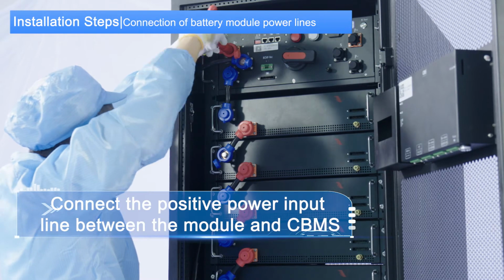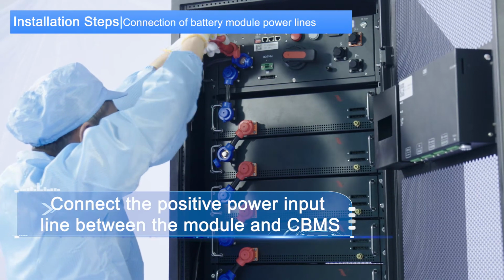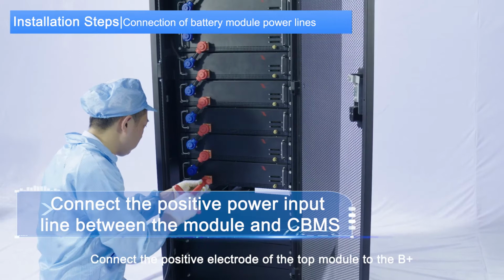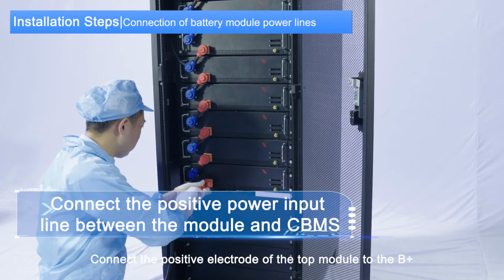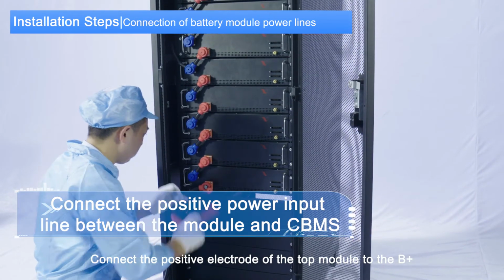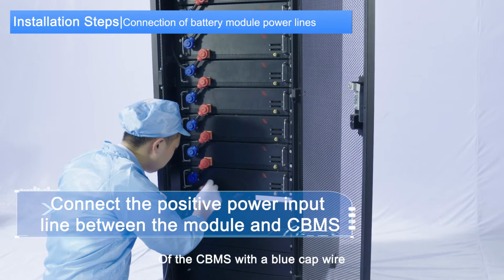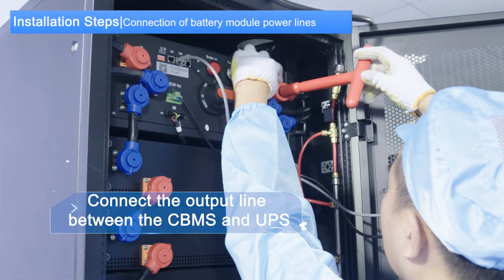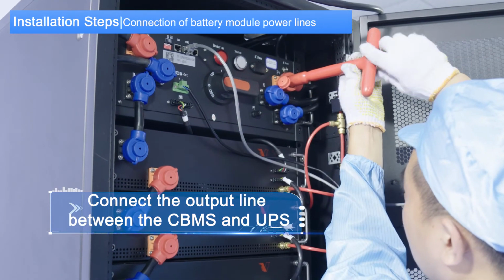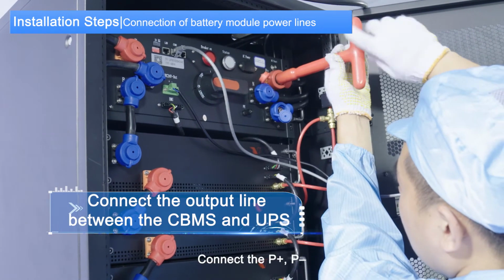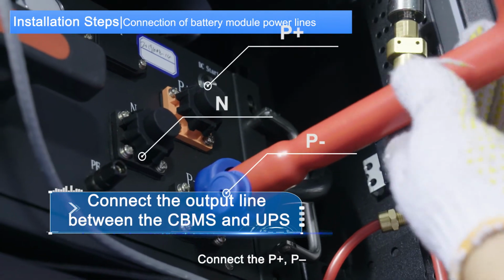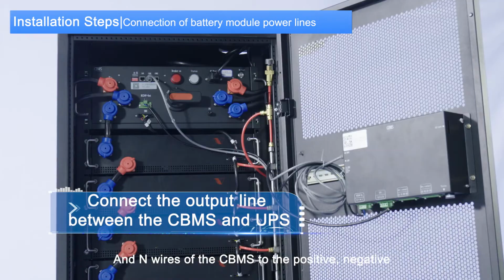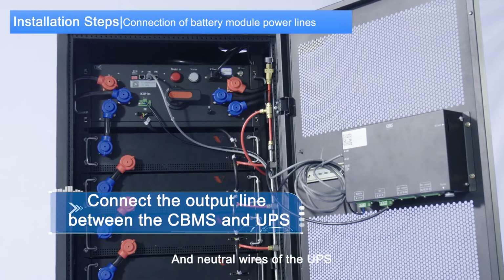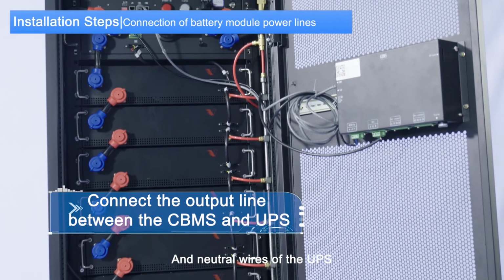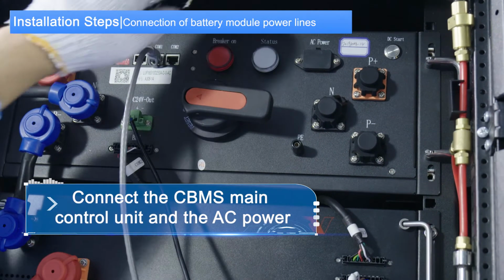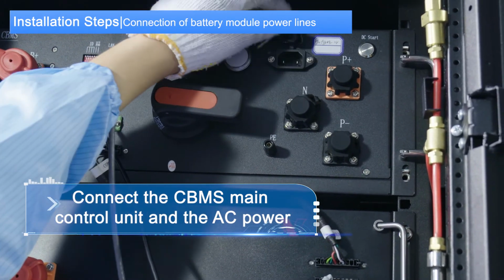4. Connect the positive power input line between the module and CBMS. Connect the positive electrode of the top module to the B positive of the CBMS with a blue cap wire. 5. Connect the output line between the CBMS and UPS. Connect the P positive, P negative, and N wires of the CBMS to the positive, negative, and neutral wires of the UPS. 6. Connect to the CBMS main control unit and the AC power.